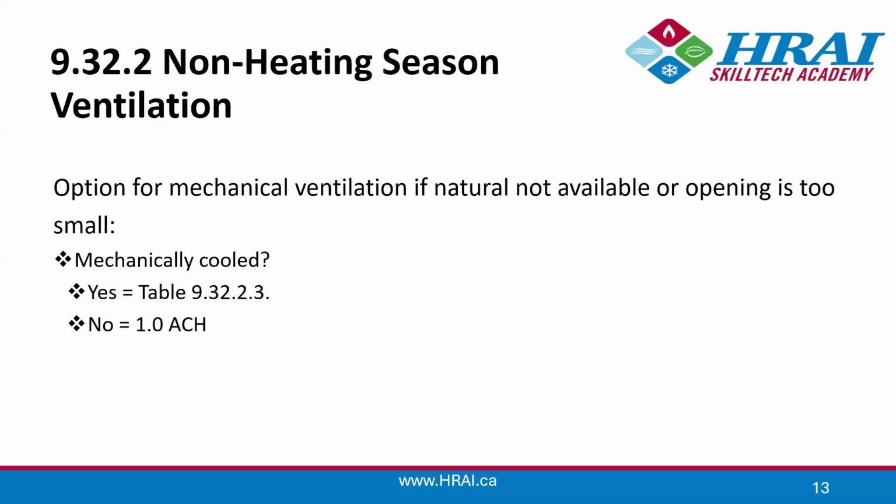If there is a desire to have mechanical ventilation, or if there is no natural ventilation, so the room does not have a window or door, then you can provide mechanical ventilation to make up for that. And then there are 2 options: is it mechanically cooled? If yes, then you follow a table. If no, then you provide 1 air change per hour. So then you'd need the volume of the room to calculate that.